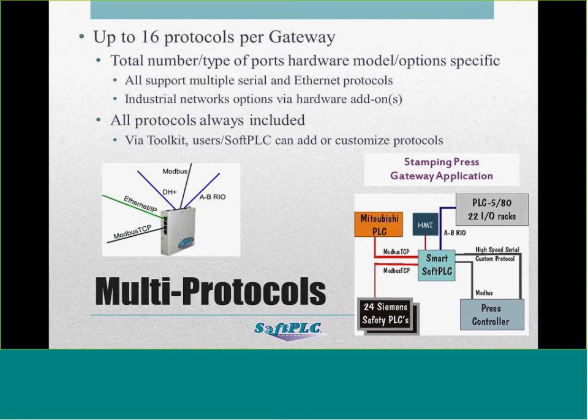And then they added a little HMI. It was actually a big screen on the wall to display status information. And that was done, I forget what software they used, but it was another Modbus TCP link. And then on the same machine, there was this press controller that communicated by a Modbus serial. And so we added that protocol, but then what happened was there was 5 words of data that had to get to the PLC-5 very, very quickly.